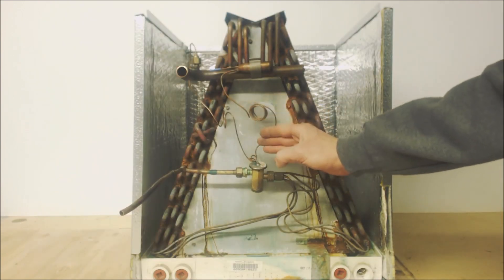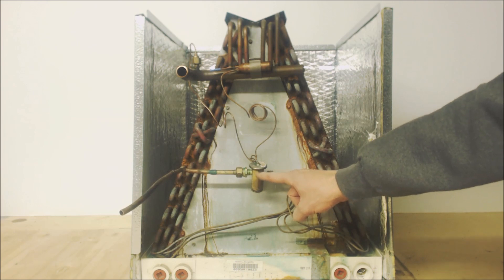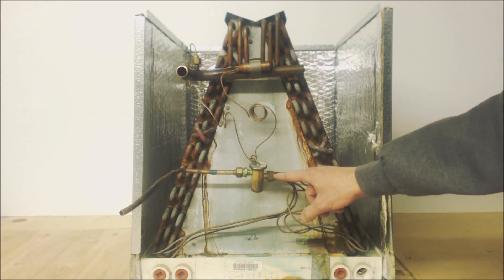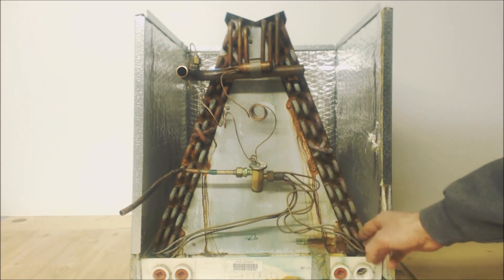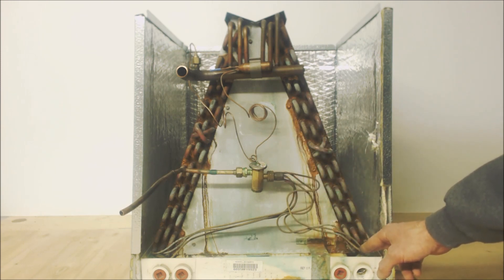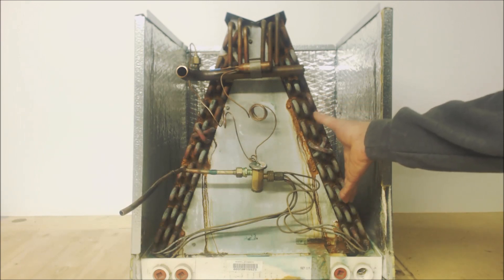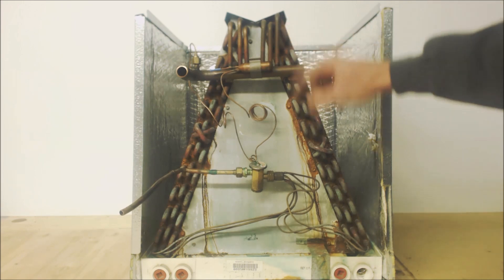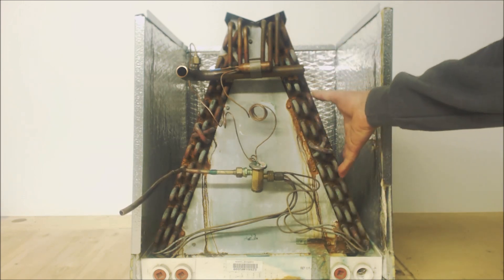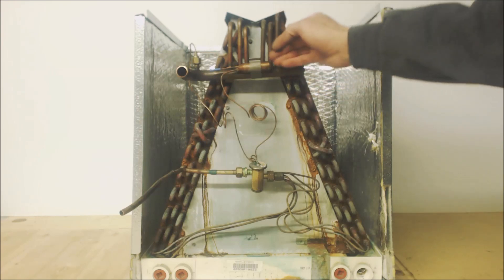This TXV controls the superheat. You have high-pressure, high-temperature liquid refrigerant coming in, it hits the metering device, and only a small amount of refrigerant is allowed through. That reduces the pressure — and temperature follows. It comes in as a low-pressure, low-temperature liquid, about 80% liquid and 20% flash gas. It then enters a saturated state where liquid and vapor both exist — that's where you absorb most of the heat from the house — and then you have your superheat above that.